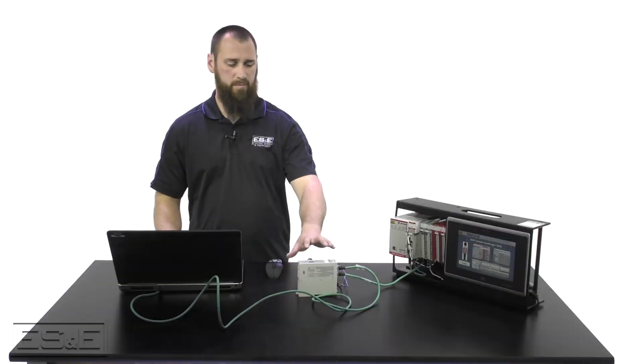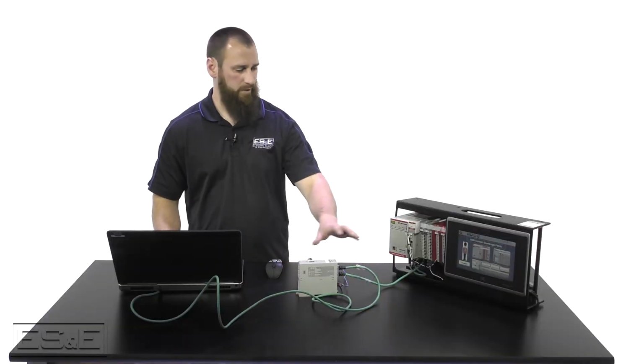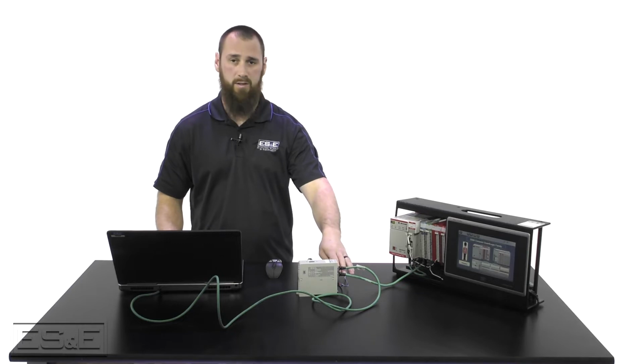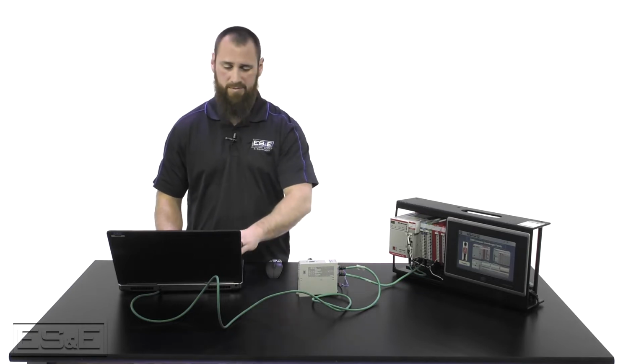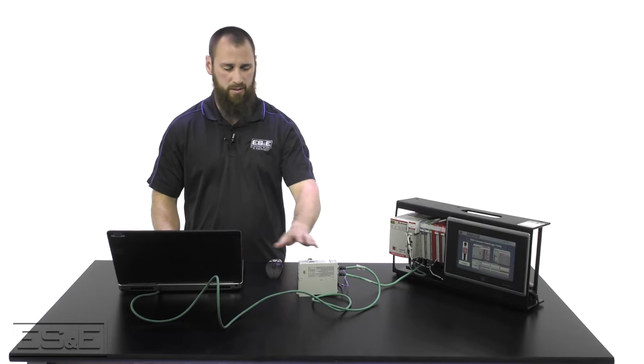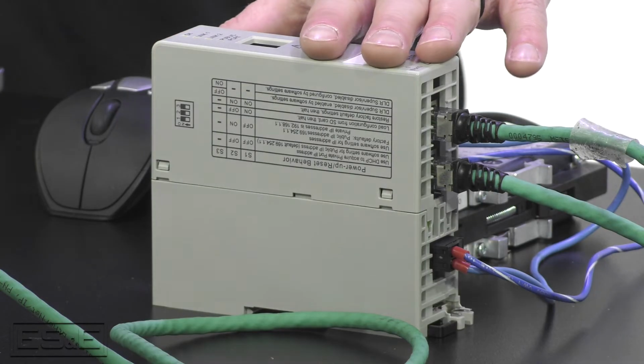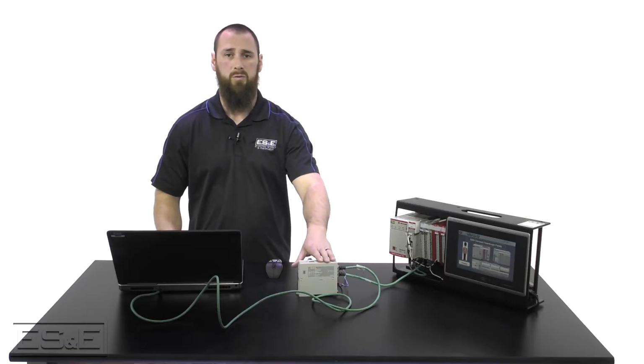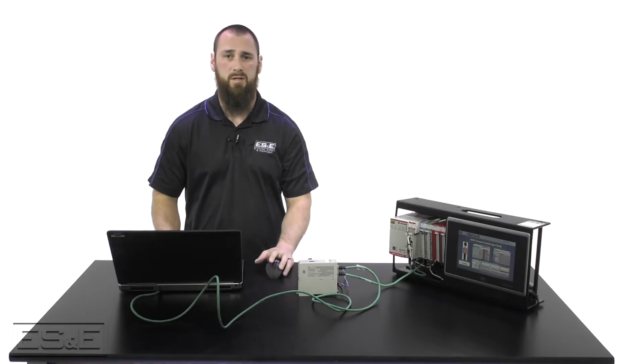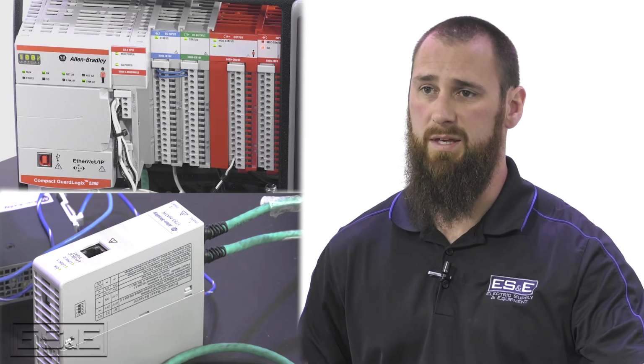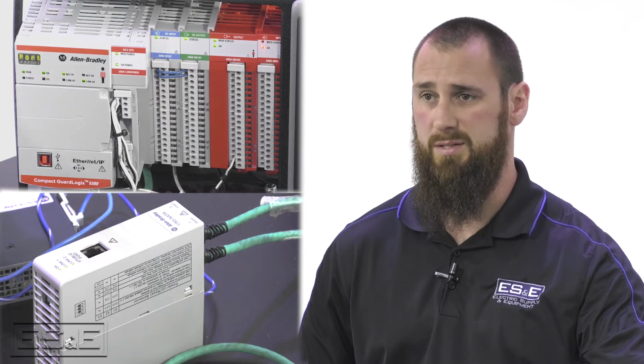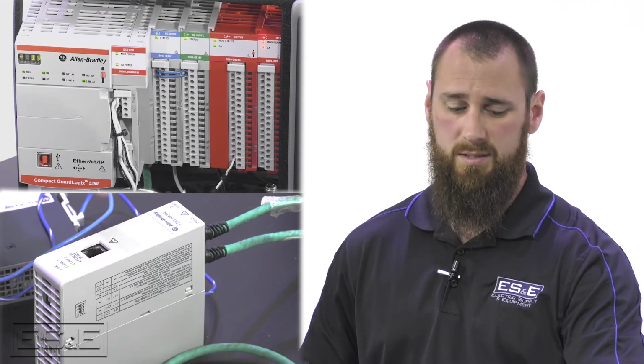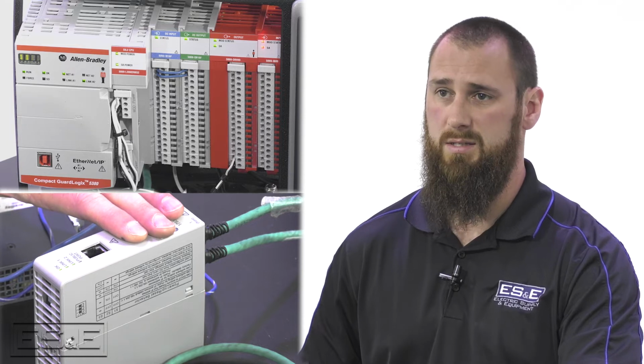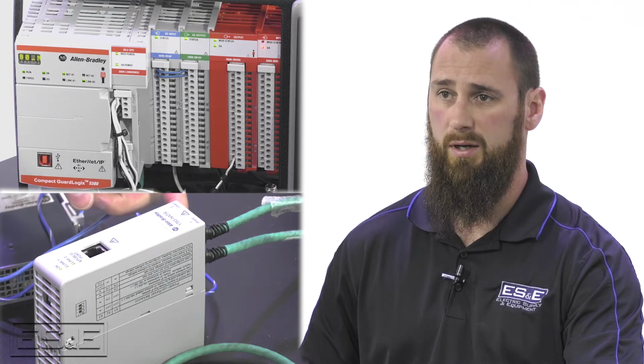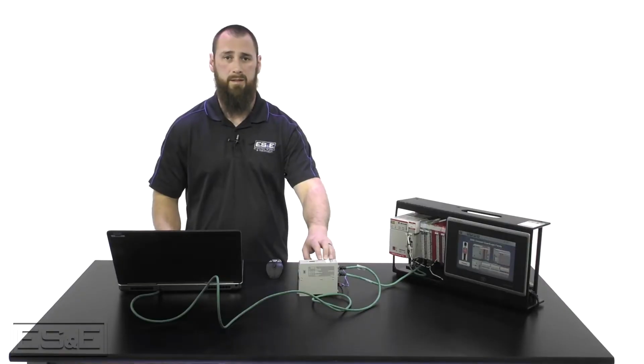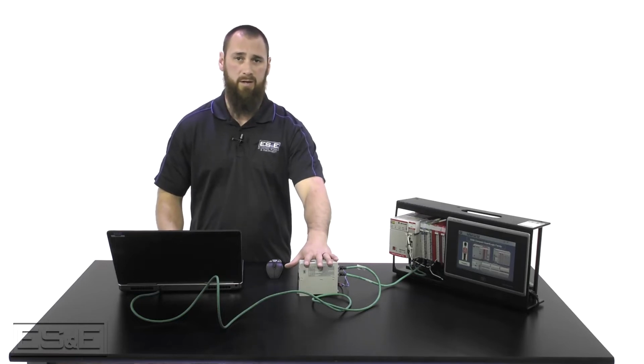Now we have powered up our NATR and we have plugged our PLC into one of the private ports, and I've plugged my laptop into the other private port of the NATR module. Now the NATR module works as a layer 3 NAT device, which means the gateway address of the physical device, which is our PLC in this scenario, needs to be the IP address of the local port on our NATR module. So we start by powering up our switch.